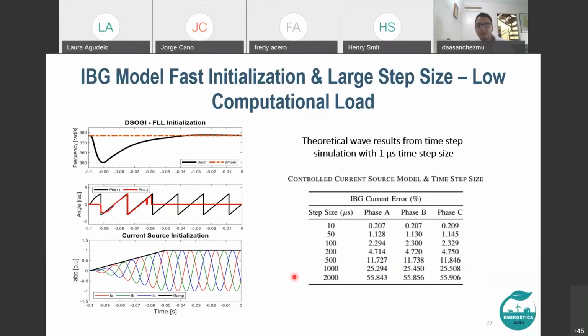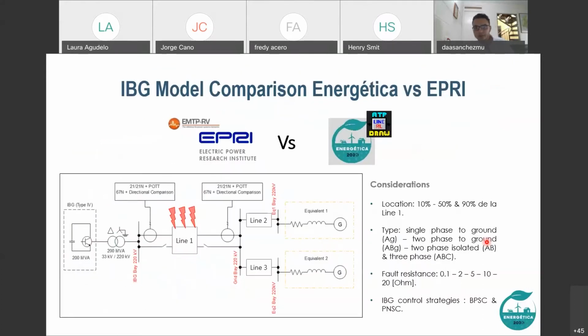Second, we check the time step requirements here. The table presents the average error for the current waveforms for the same fault event simulated with different time step sizes. Here we highlight that the implemented model can work with a time step of 100 microseconds with errors below 3%. Usually 100 microseconds for time step size in an EMT inverter-based generation model is a pretty large time. Then, as I told you, in the Energetica world map, we make a comparison between our model and the EPRI model. EPRI is a very respected research institute.